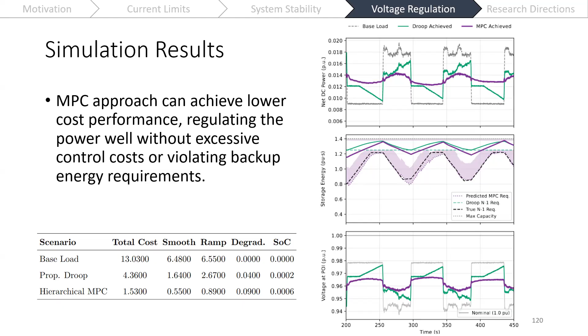Zooming in a bit here, we can see how the model predictive controller has this purple buffer around our predicted dotted purple line for that lower limit, and our control value skirts along the top of that buffer, being able to utilize a little bit more headroom than the droop control case can. It's also more optimally dispatching our storage to smooth our load profile to look something like this here, where we have lower ramps and less deviation from that minimum value, resulting in an overall lower cost for our hierarchical approach than this proportional droop control.